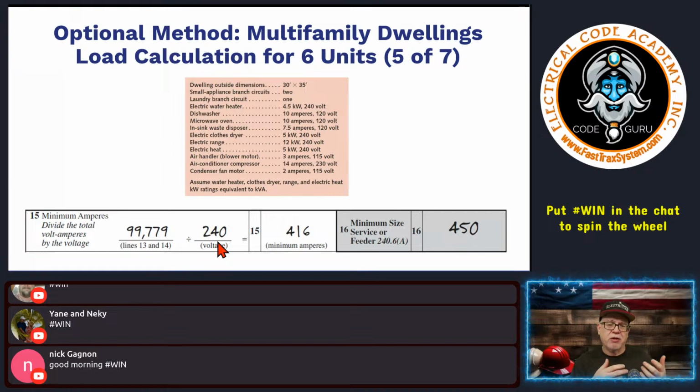The only thing you have to be careful about is the actual water heater, and we're just using nameplate values from the water heater. So it's an assumption that that's a 208 volt rated water heater, okay? But it's not until you're three-phase that you have to worry about the 1.732 factor, if it's truly three-phase to that water heater. If it's not, it's usually going to be single phase, whether it's 208 single phase or 240 single phase. So I think they were overcomplicating it.